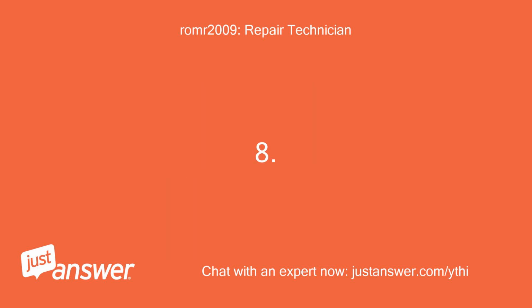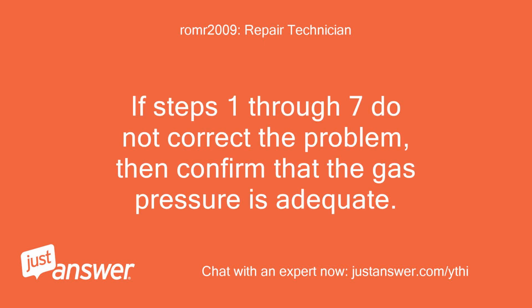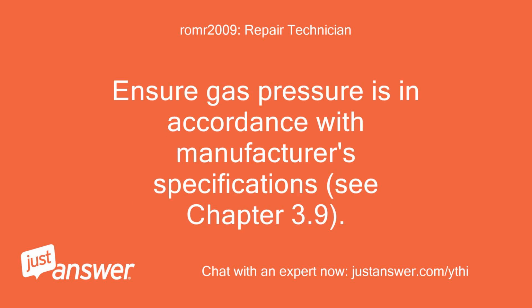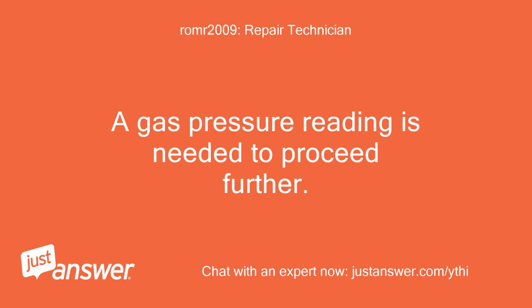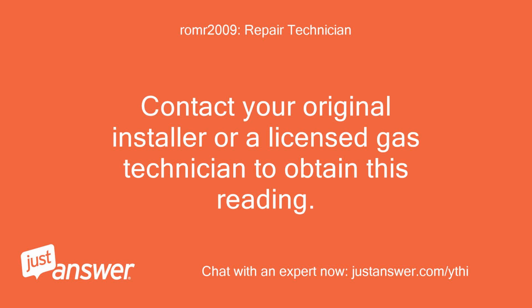8. If steps 1 through 7 do not correct the problem, then confirm that the gas pressure is adequate. Ensure gas pressure is in accordance with manufacturer specifications, see Chapter 3.9. A gas pressure reading is needed to proceed further. Contact your original installer or a licensed gas technician to obtain this reading.